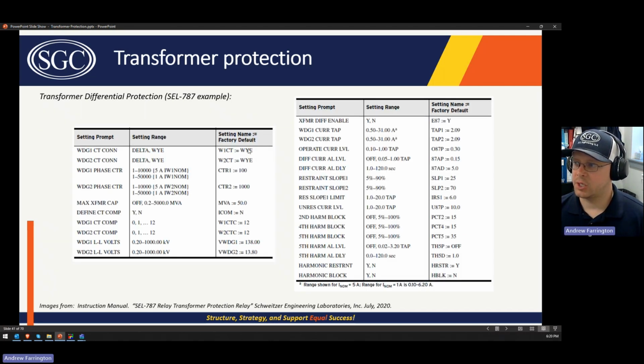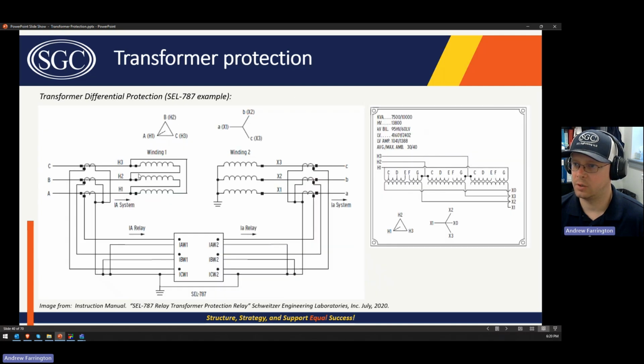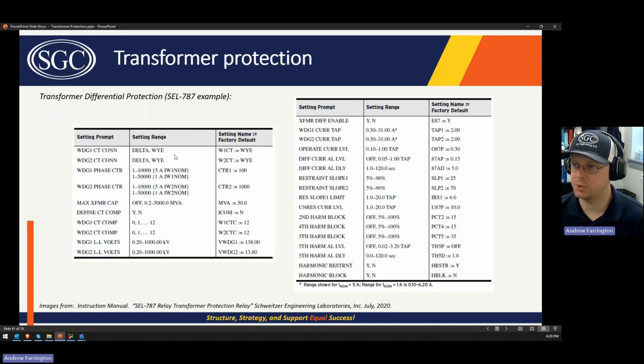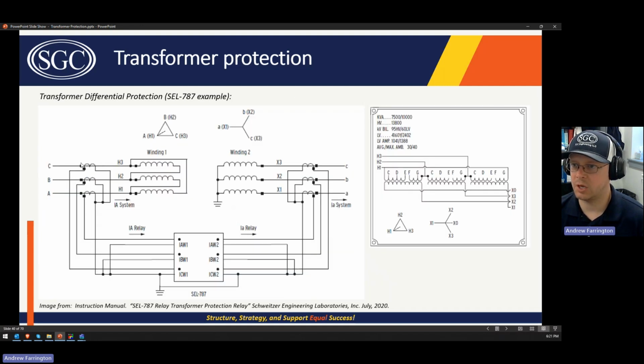So these here are the settings that you're basically always going to have to set regardless of the relay manufacturer or model. And then these are the ones that are kind of subject to the type of relay that you're using. So winding 1 is the CT connection for winding 1, which we already talked about. Both CTs are wired in a Y. So you'd set the winding 1 CT connection to Y and the winding 2 CT connection to Y. The winding 1 phase CT ratio, well, that's pretty self-evident. It's not actually depicted on here, but you'd select the CT ratio for that particular CT. How do you determine the CT ratio? We kind of covered that.